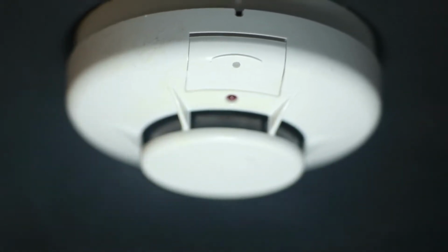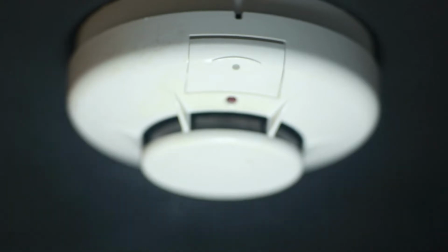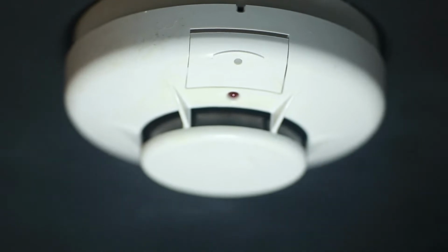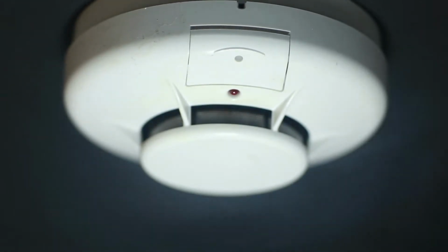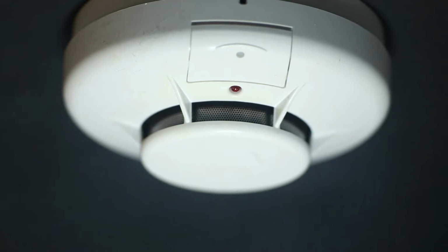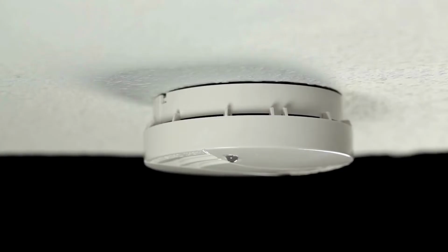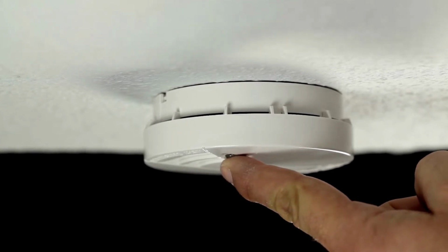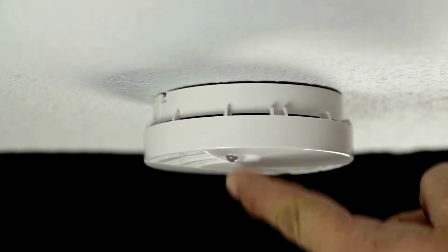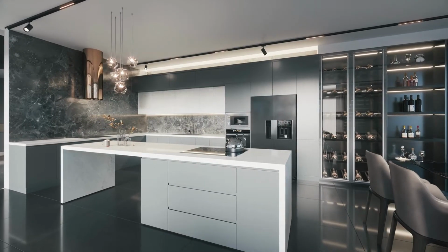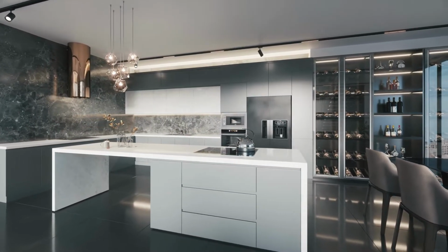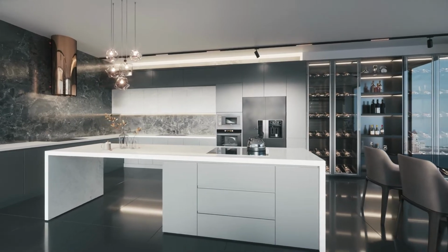Heat sensors. Heat detectors sense heat from a fire and signal your alarm to alert you. A fire normally causes a quick rise in temperature in the vicinity of its occurrence. Heat detectors can either go off when detecting high temperatures, often when the temperature reaches 135 degrees Fahrenheit or greater, or when it detects your temperature rising at an unusually rapid rate. Heat detectors are typically installed in areas where you expect smoke or dust, like kitchens, basements, furnace and laundry rooms, hallways, stairways, garages, attics, and fireplaces.